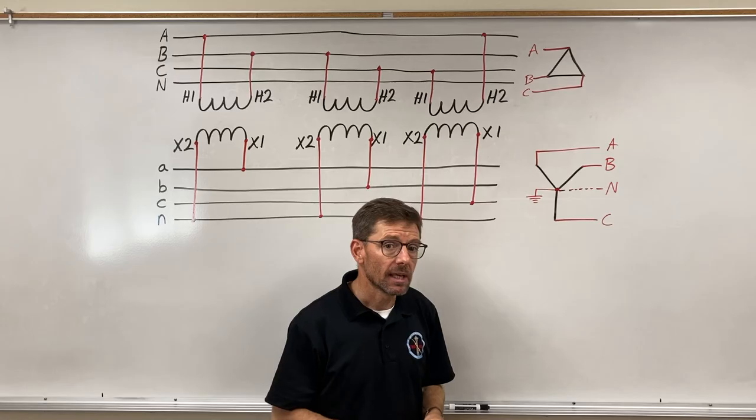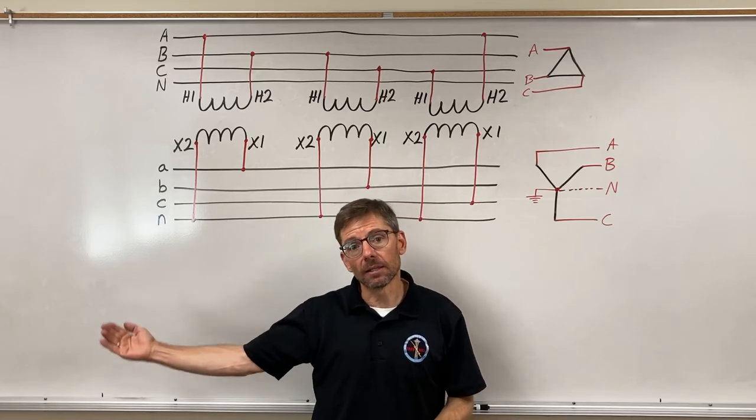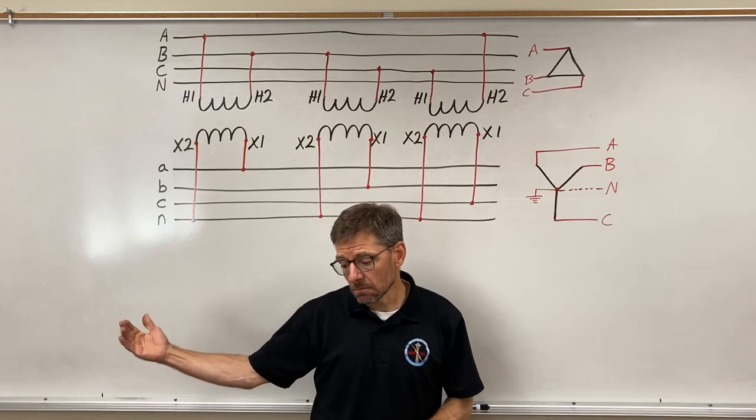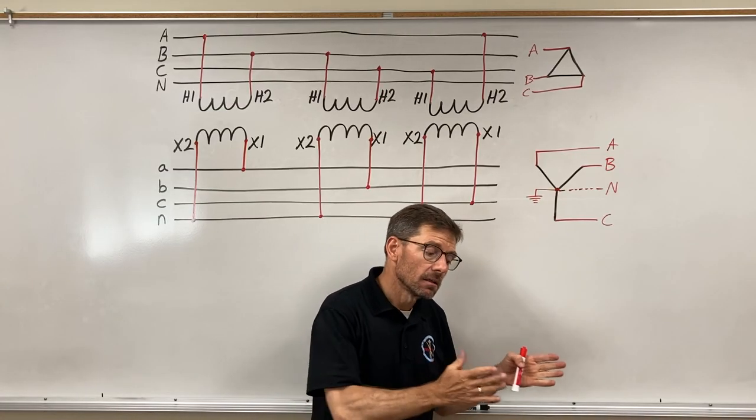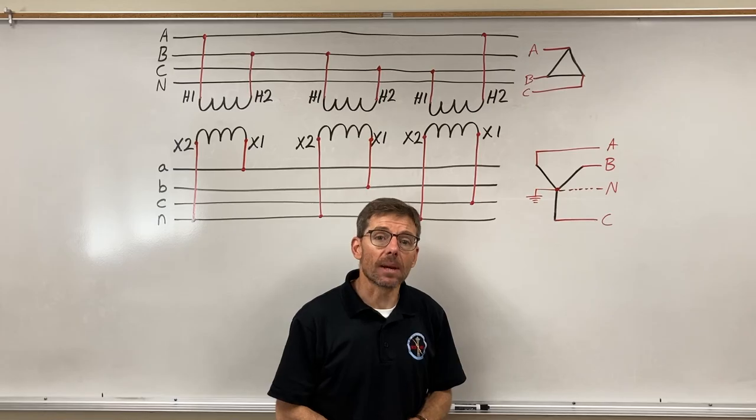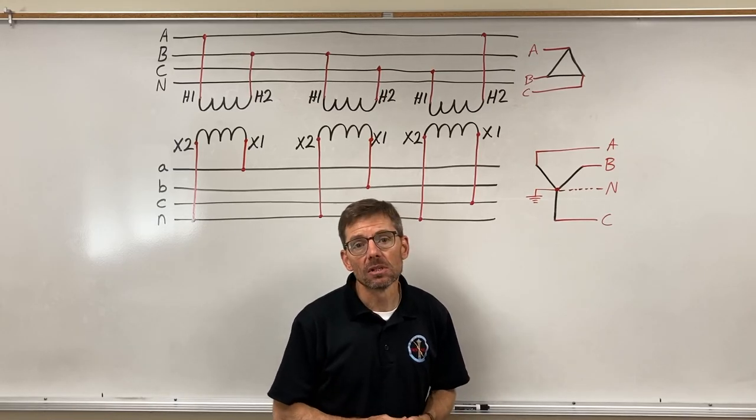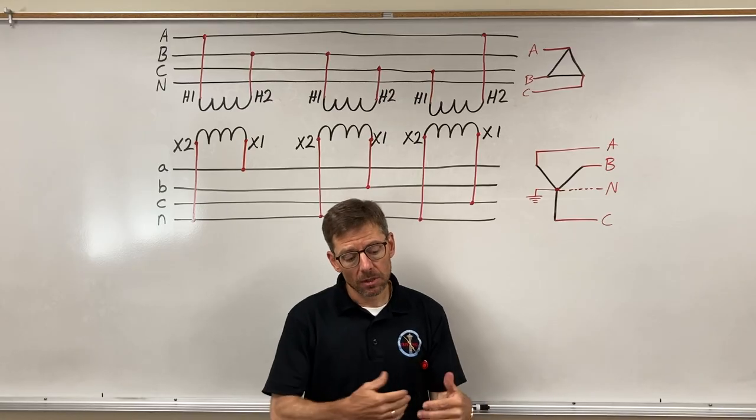And also at the main service. So at the main, and then at your separately derived systems, which generally means most transformers that don't have a connection between primary and secondary.